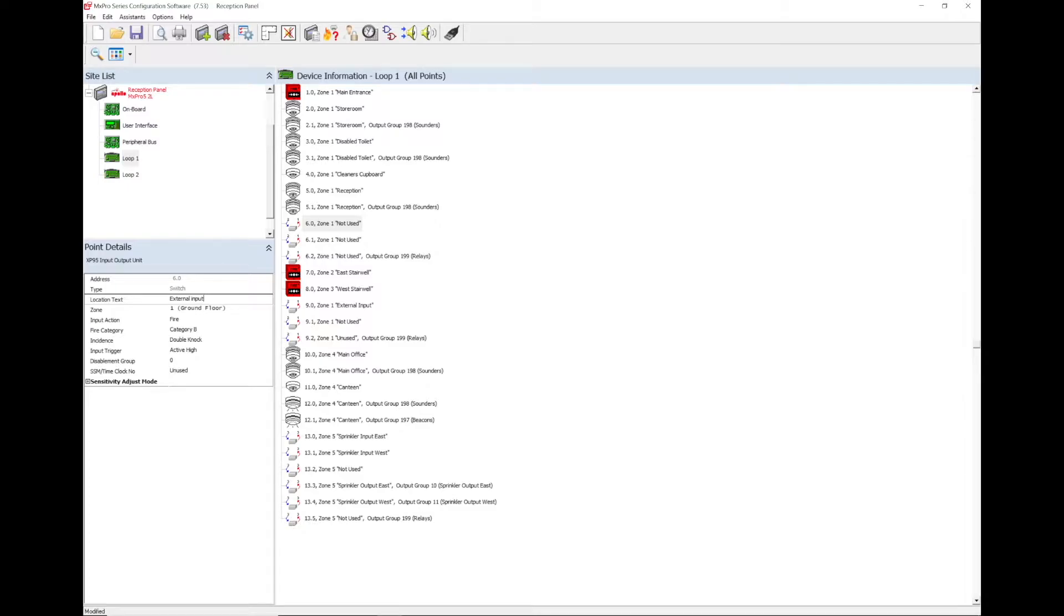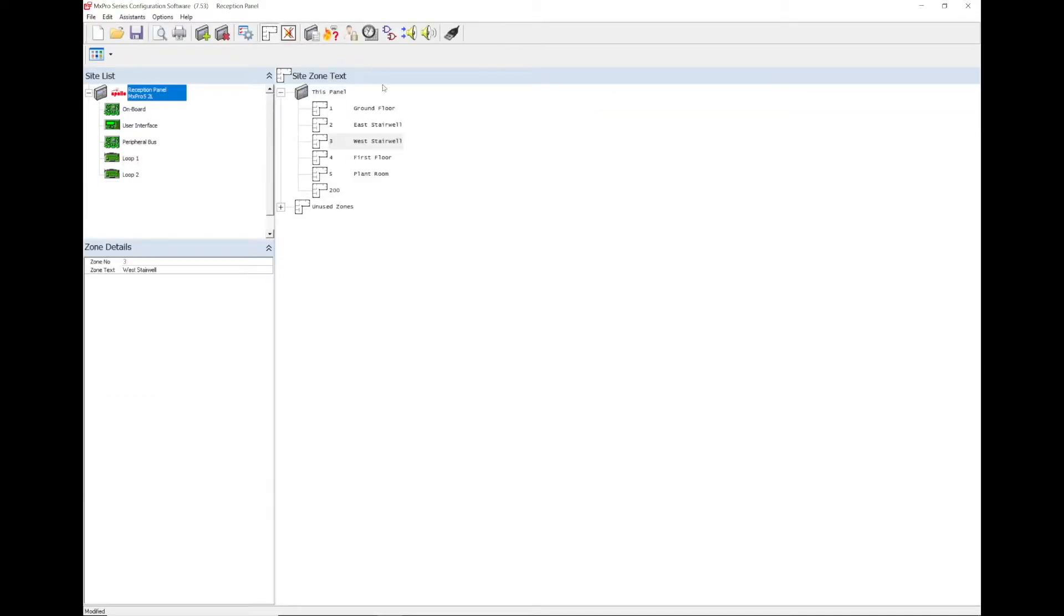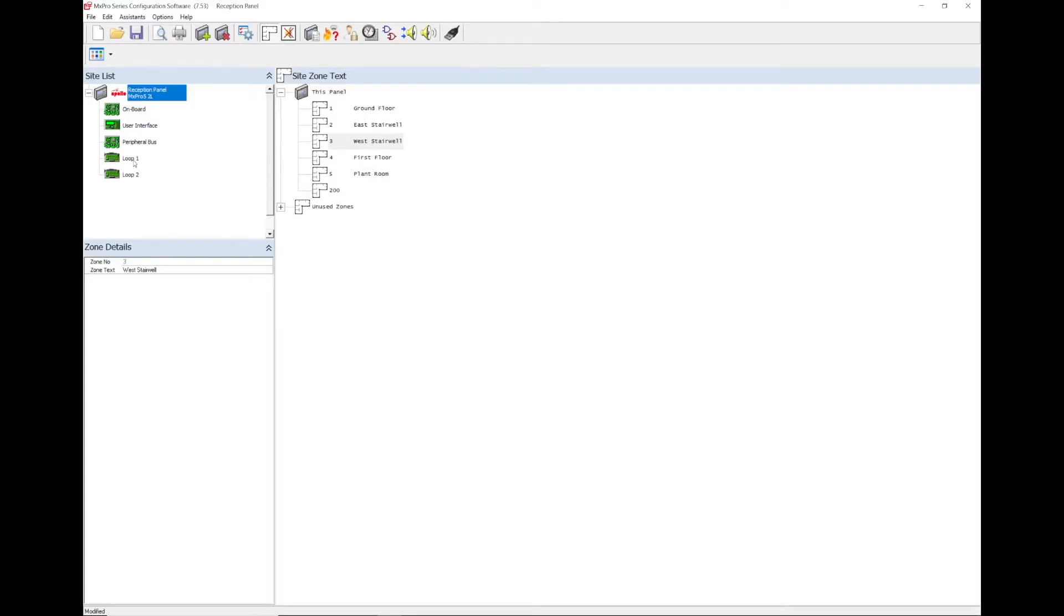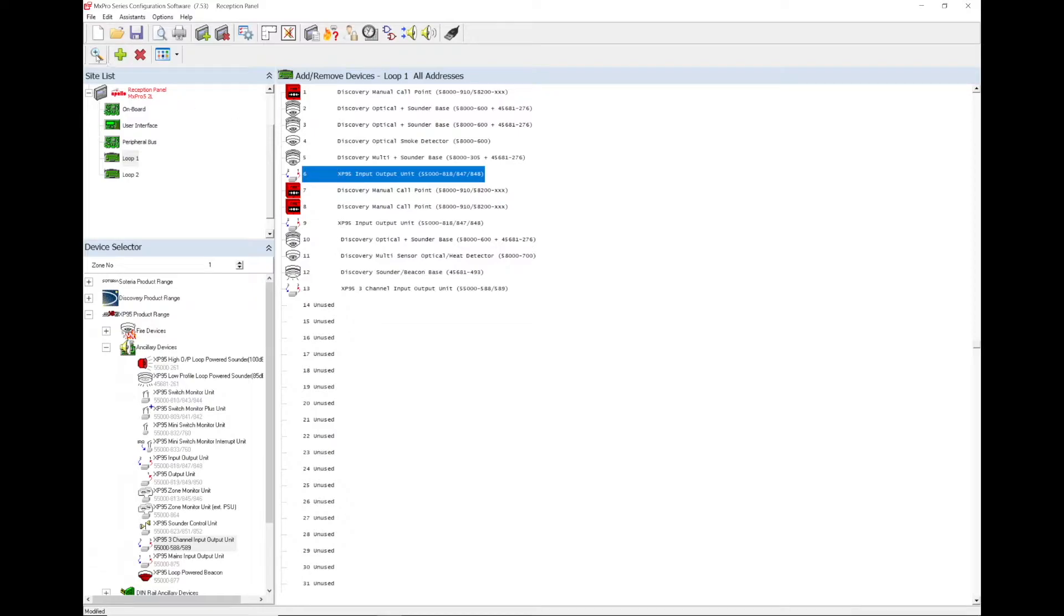Choose a zone that is not currently being used. To find an unused zone, go to view edit zone text from across the top row of icons and choose any zone that is not in this list. On this config, zone 50 is spare so this can be used. Back on the input, the zone can then be changed to zone 50.